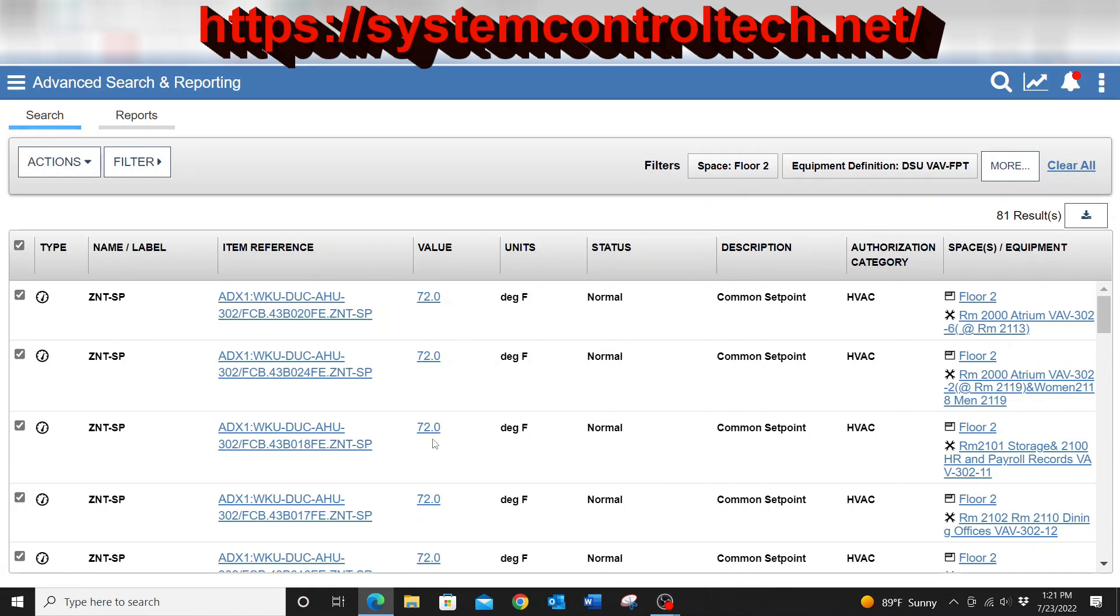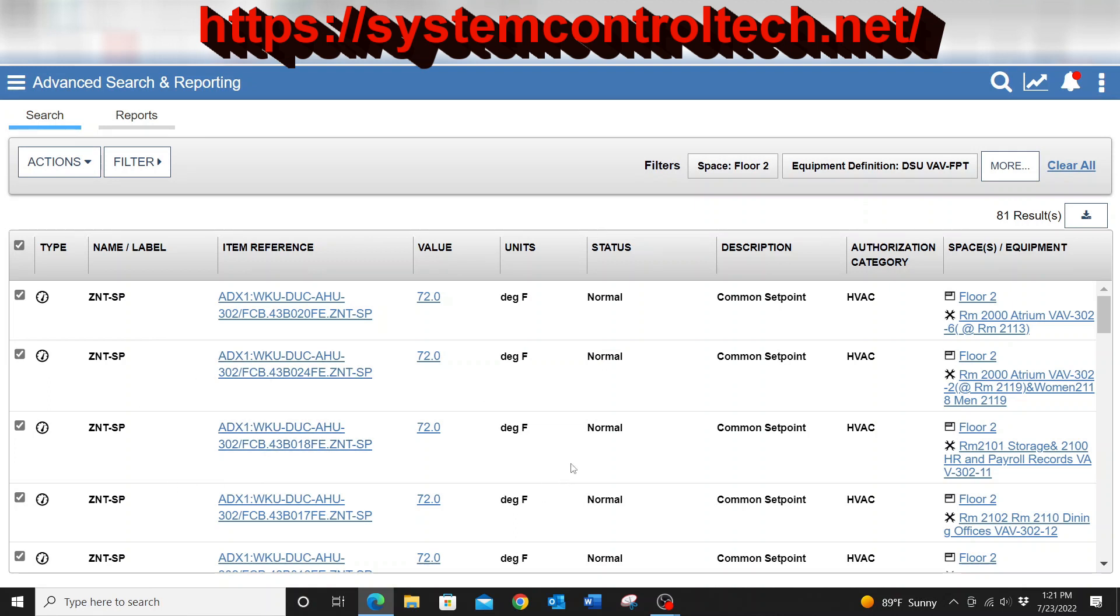Now, if you have different types of controllers that get pulled into this list, and just for example, if you have a building to where one part of that building is for an N2 device and another part is a BACnet device, this type of bulk commanding will not work properly. It will give you an error when you try to do that. However, the controllers that are consistent, you can group them together in something like this.